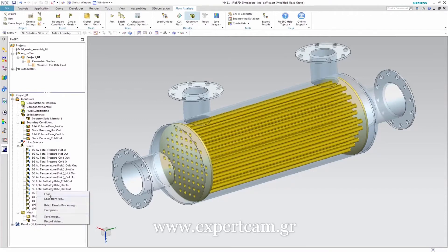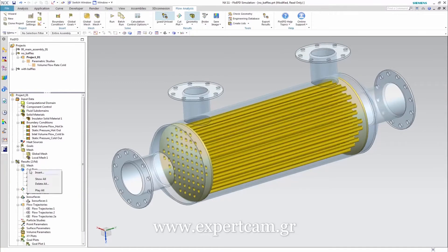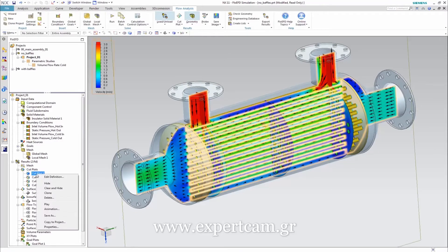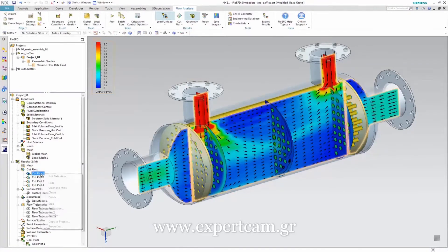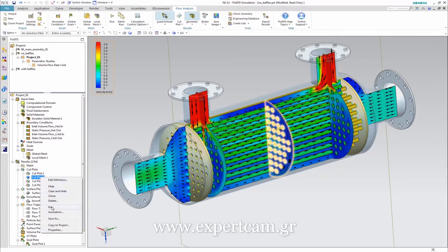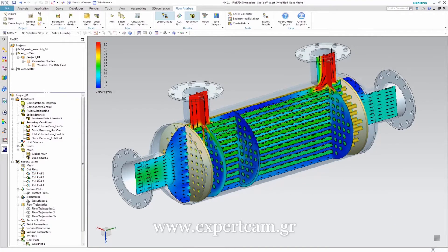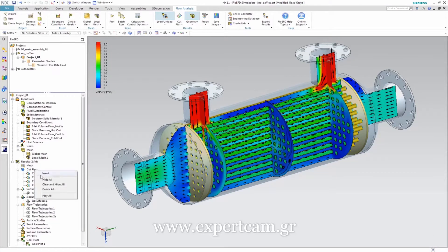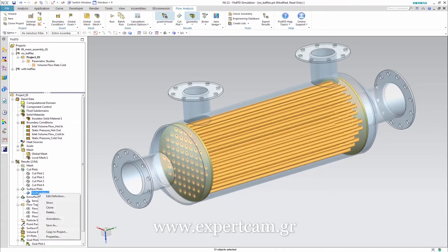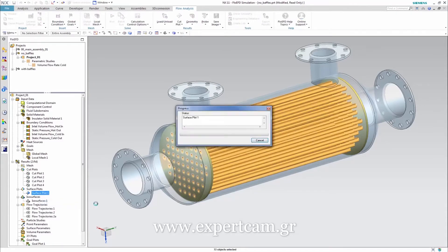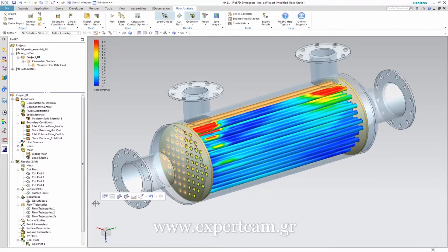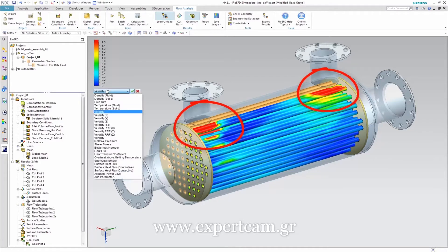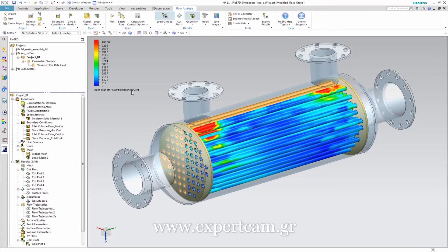Let's take a look at some of the results. We can create multiple cut plots and we can let them move through the model automatically, defined by the corresponding planes. The surface plots are a three-dimensional plot and these show the results on the tube outer surfaces. For the velocity, we can see the highest velocity at the inlet and outlet area. Let's switch the display parameter to the heat transfer coefficient — we can observe the highest heat transfer coefficients in the same regions.